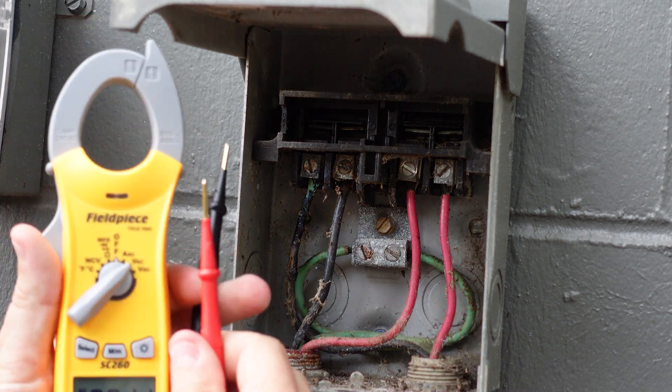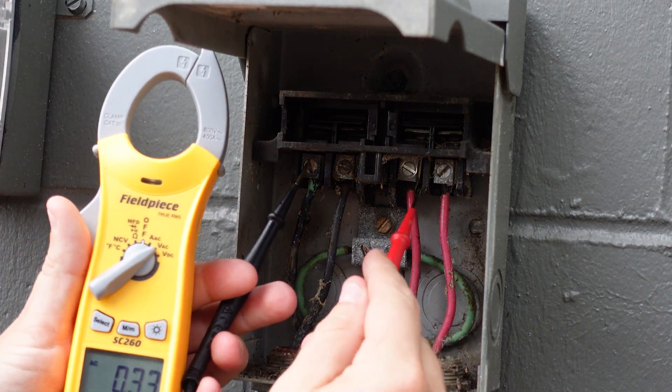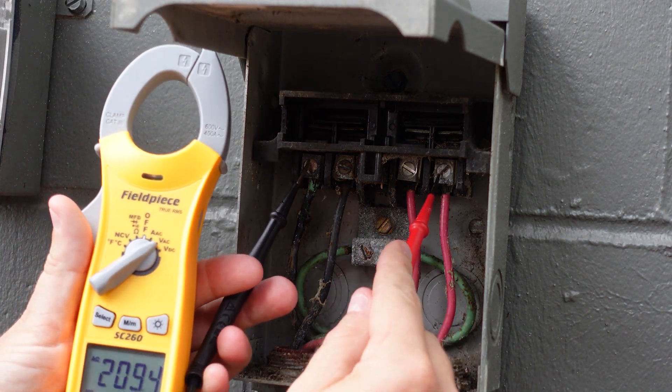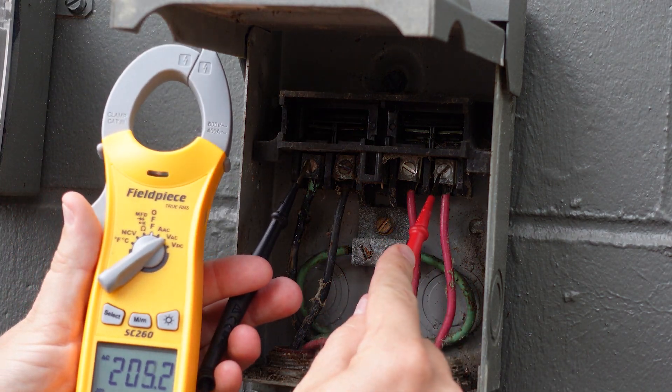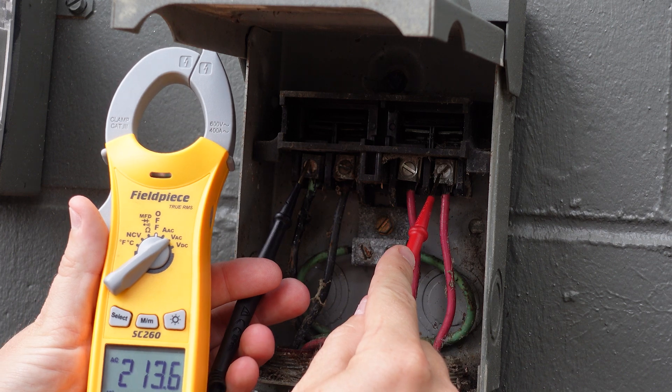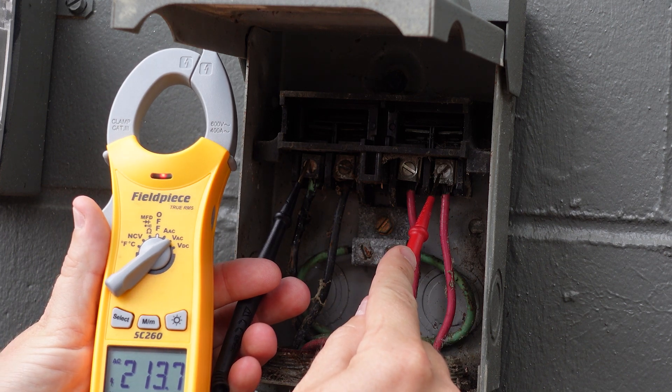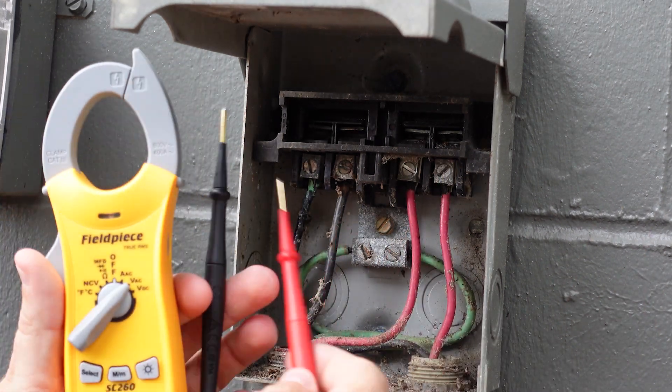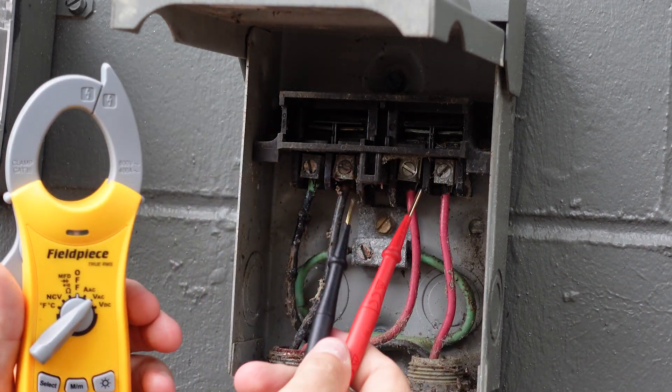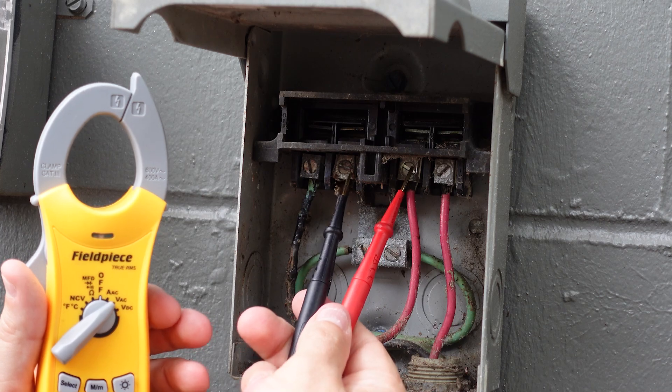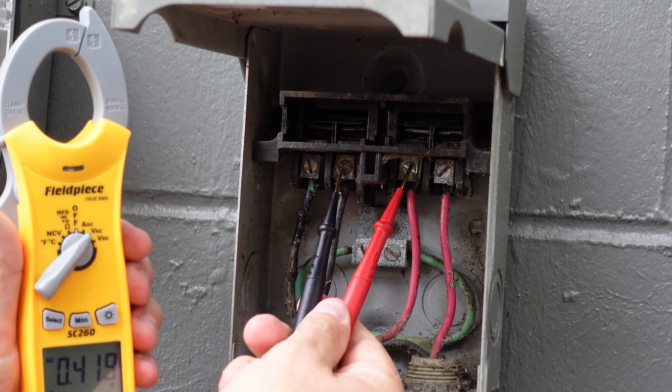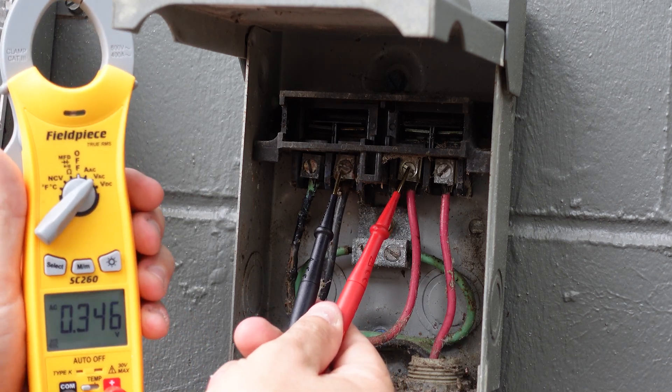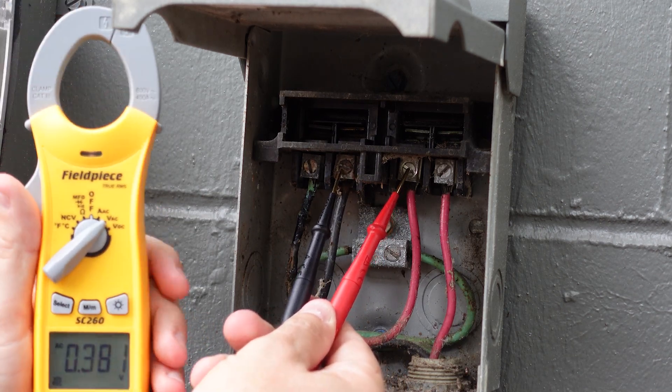But let's confirm here that we have voltage on our outside poles. And we do. 213 because this is a 208 structure. And that means that because our disconnect is pulled, we should not have voltage here.